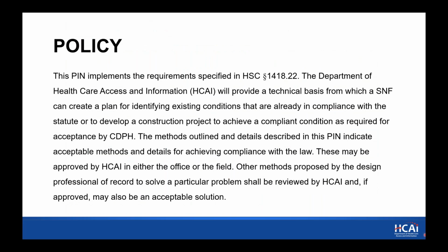So our policy implements the requirements specified in Health and Safety Code 1418.22. That's where AB 2511 ended up. HCAI will provide a technical basis for which a SNF can create a plan for identifying existing conditions that are already in compliance with the statute, or to develop a construction project to achieve a compliant condition as required for acceptance by CDPH. The methods outlined and details described in this PIN indicate acceptable methods and details for achieving compliance with the law. These may be approved by HCAI in either the office or the field. Other methods proposed by the design professional of record to solve a particular problem shall be reviewed by HCAI, and if approved, may also be an acceptable solution.